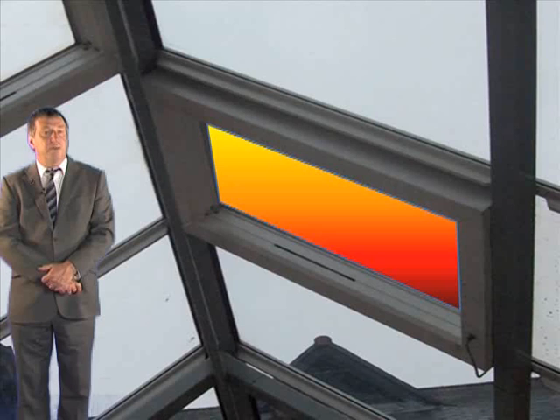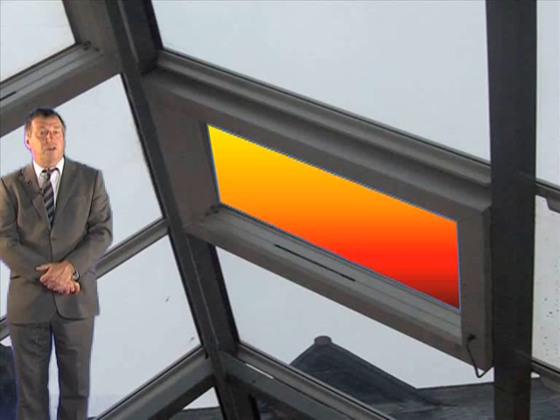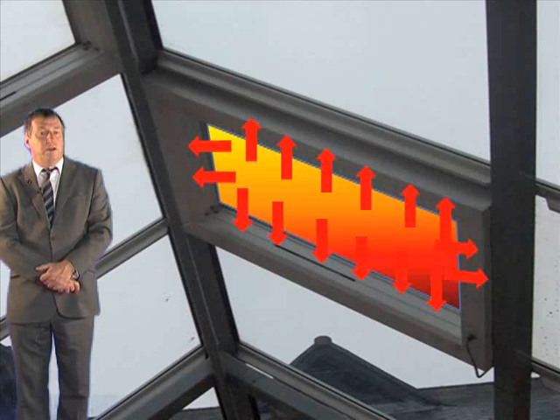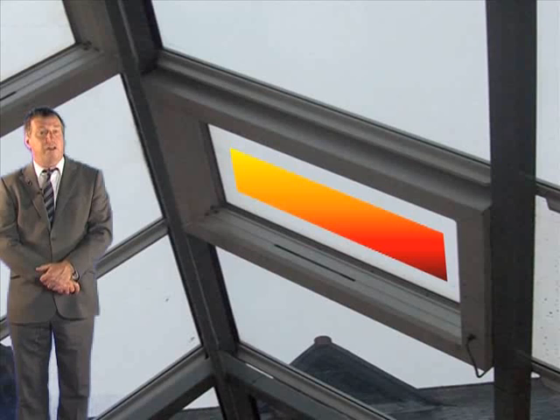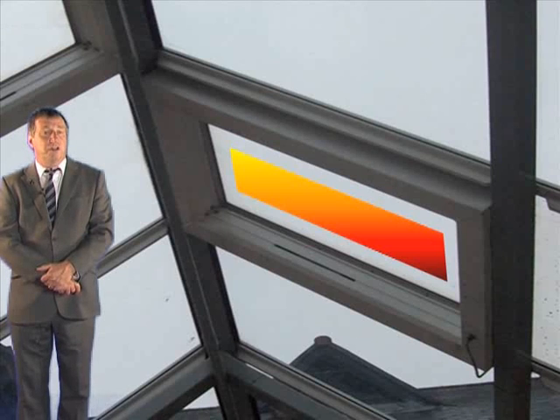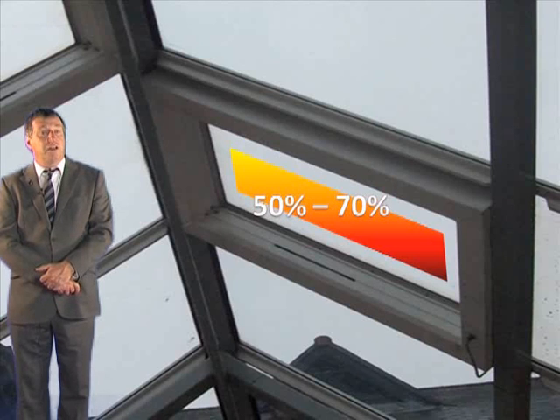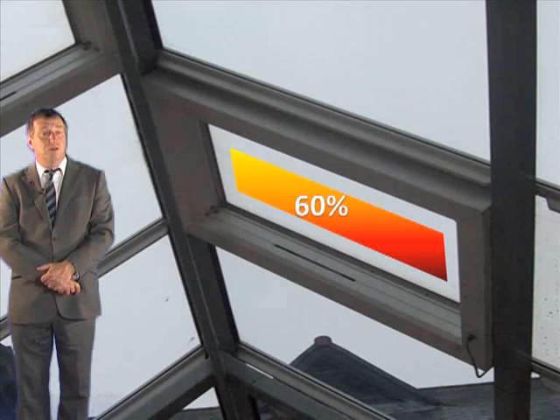Every ventilator has a geometric area, and that is the measured size of the hole that it produces when it opens. But that geometric area is not 100% efficient, as there is considerable turbulence around the edges. So there is a proportion of the geometric area that is actually useful in terms of providing an effective opening, and that proportion is the aerodynamic free area. The proportion varies from ventilator to ventilator, but is usually in the range of 0.5 to 0.7, or 50% to 70%. Many ventilators are around 60% efficient, and so a default proportion of 0.6 or 60% is usually assumed when more precise details of the ventilator are not known.